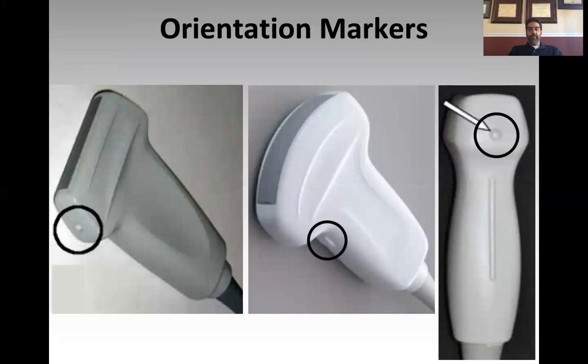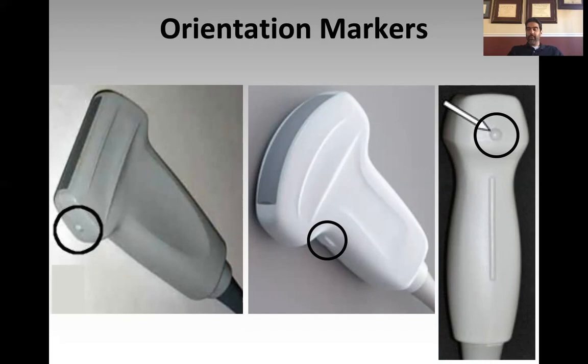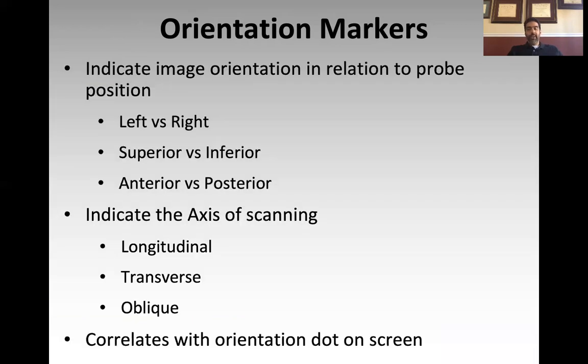I think you're all familiar with orientation markers, but let me talk about that quickly. The orientation markers are various markers on the probe and on the screen that help you orient your image. These are some examples of how various orientation markers appear on different probes — some are dots, some have a raised line or ridge as the orientation marker. The orientation marker gives you two things: it helps you orient your image in relation to the probe position — left and right, superior versus inferior, anterior versus posterior — all correlating with where the indicator on the probe is on the patient and where the dot is on the screen.